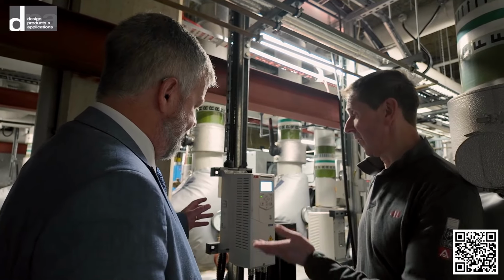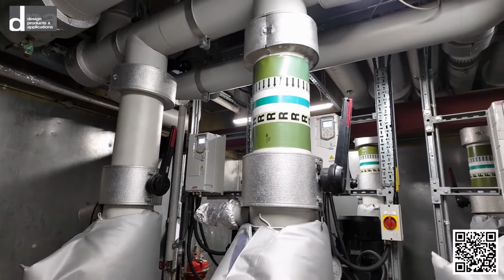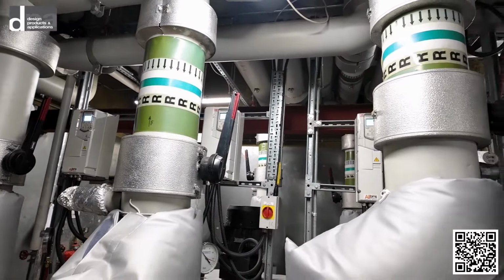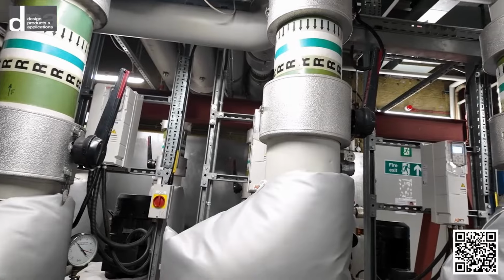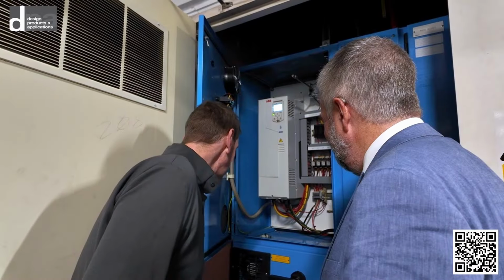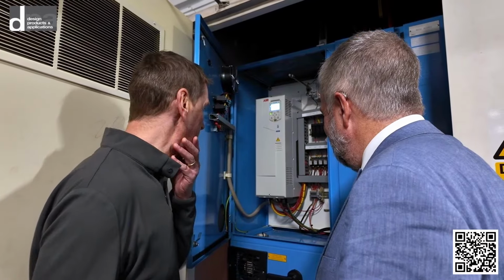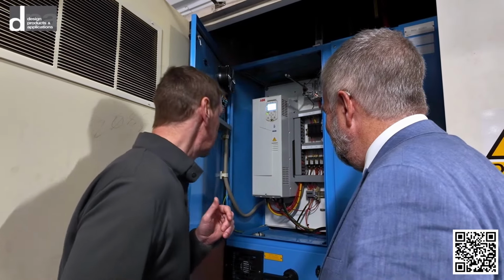If systems are conventionally controlled, that really lends itself to installing variable speed drives, a real opportunity to save energy and reduce CO2. Basically what we do is look at the absorbed power, take measurements, compile a report, and feed that back to the facility manager, or if we're working with a system integrator, we work with them to give that to the facility manager or end user.